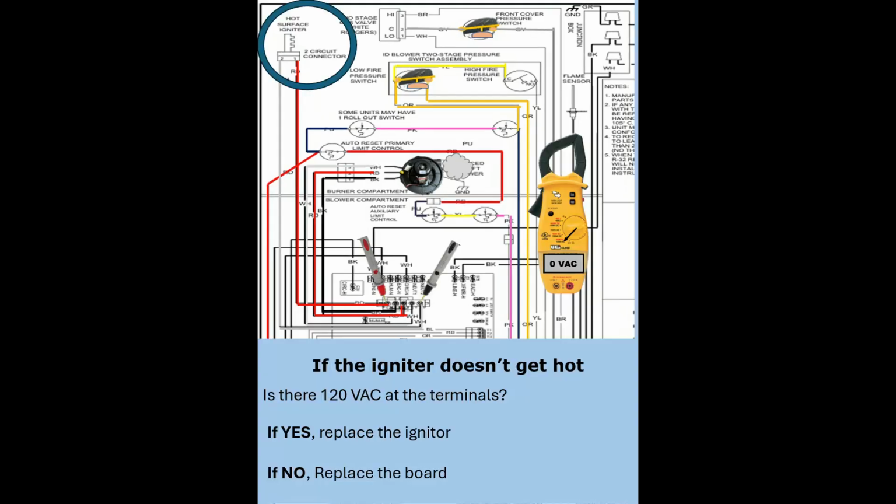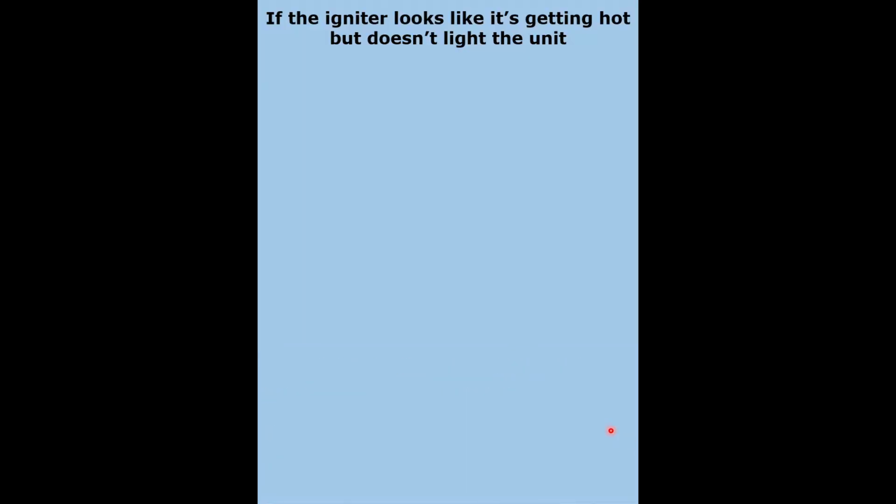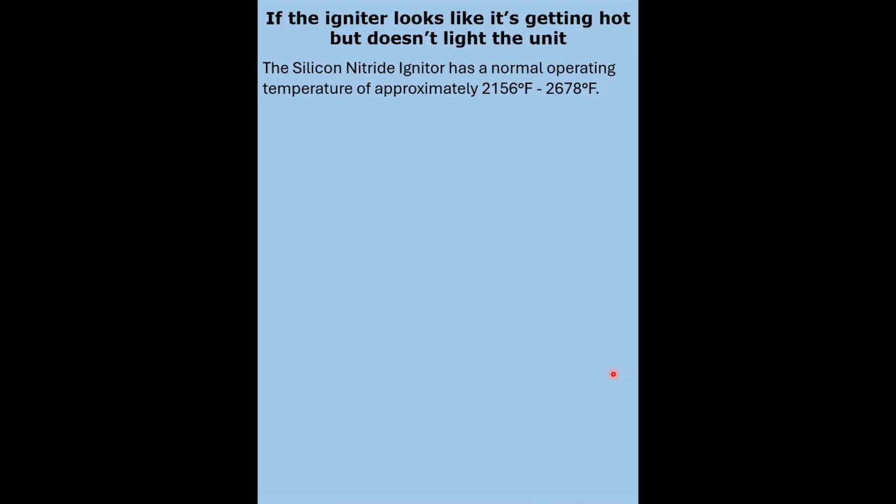So if the igniter doesn't energize, if the igniter doesn't get hot, is there 120 volts at the terminals? If yes, replace the igniter. If no, replace the board.